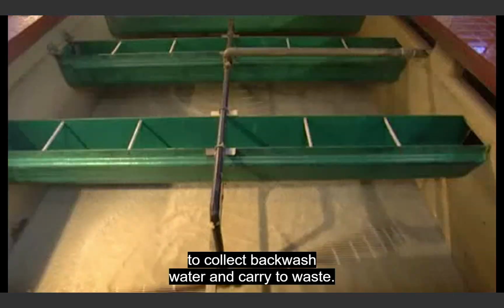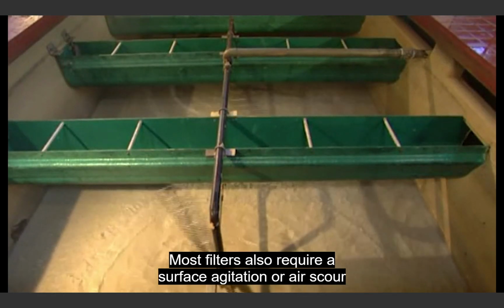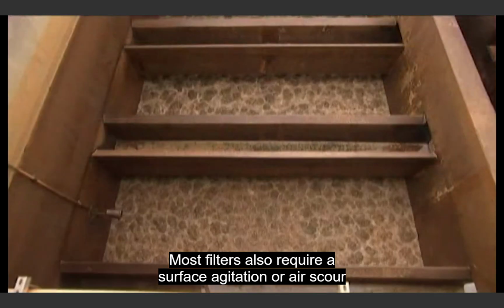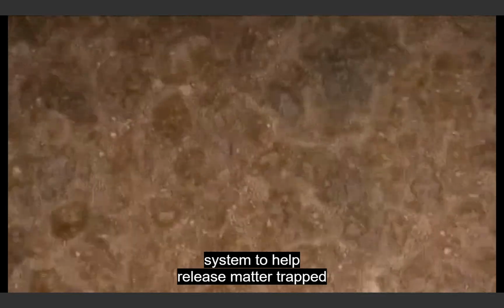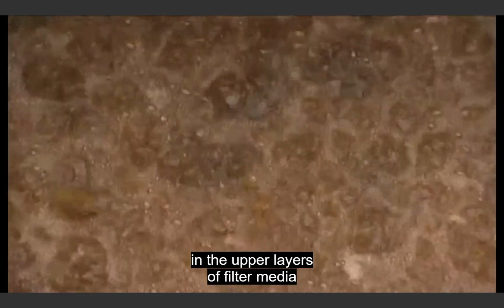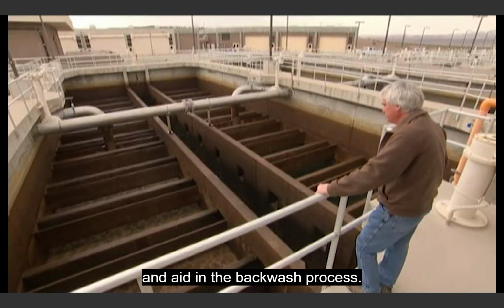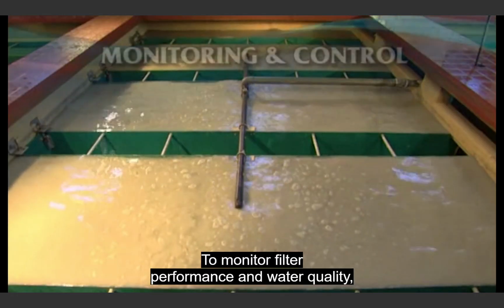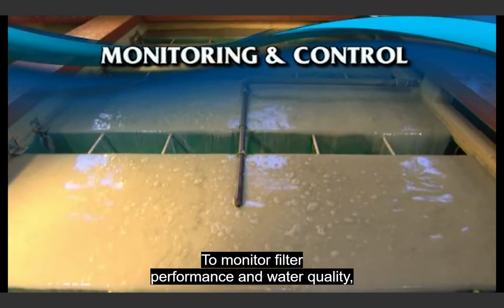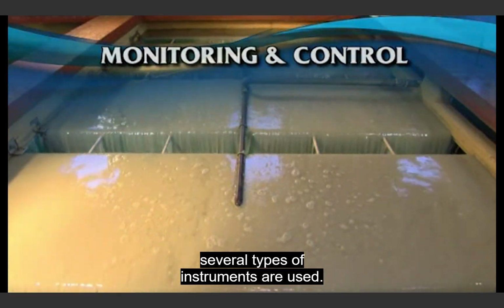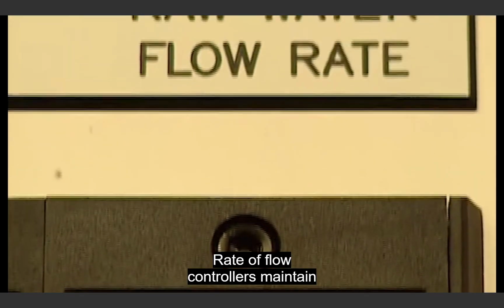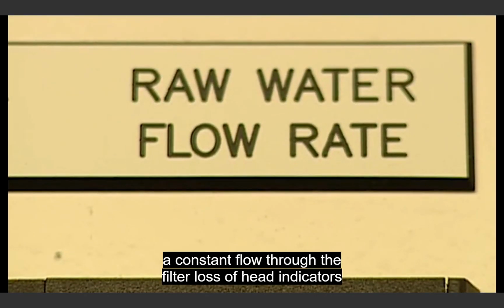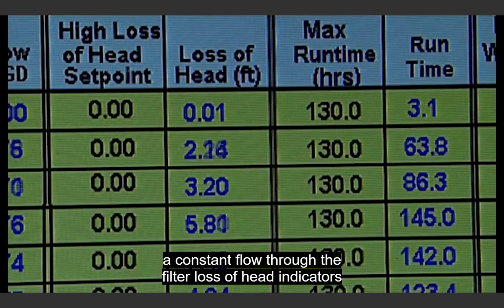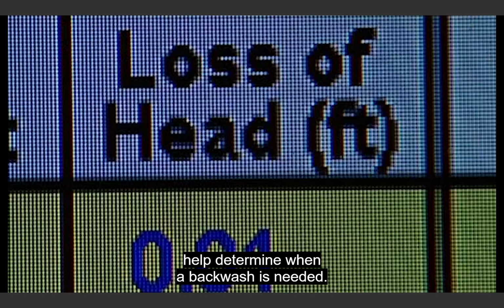Most filters also require a surface agitation or air scour system to help release matter trapped in the upper layers of filter media and aid in the backwash process. To monitor filter performance and water quality, several types of instruments are used. Rate of flow controllers maintain a constant flow through the filter. Loss of head indicators help determine when a backwash is needed.